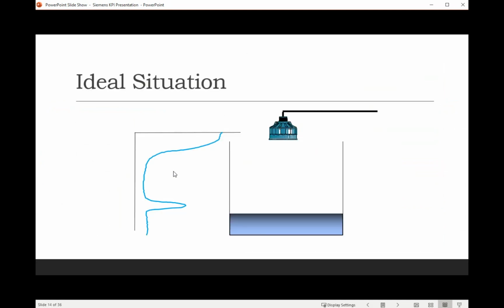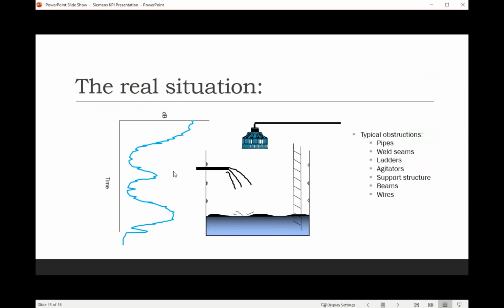In an ideal situation, you have a tank, no obstructions, and a clear path for the transducer signal and echo. If you look on the left, this is what we call an echo profile. Your transducer is sending a signal down, getting an echo off of the water, that's what you can see over there, and with no obstructions, it's a beautiful signal.